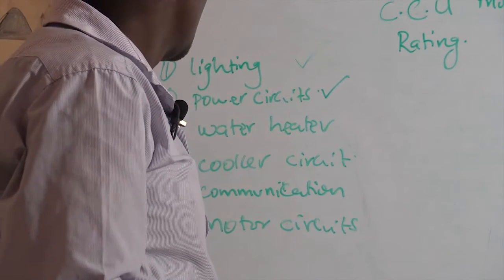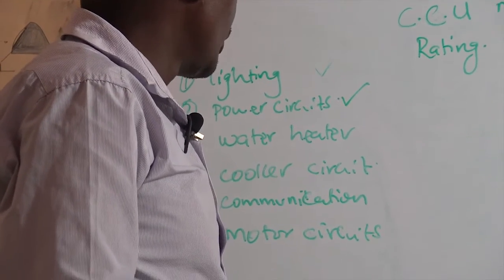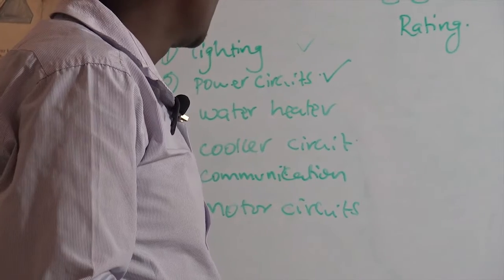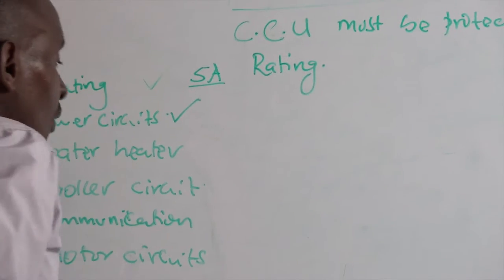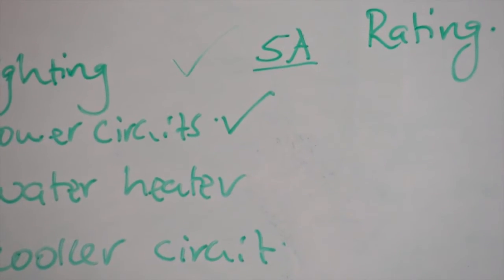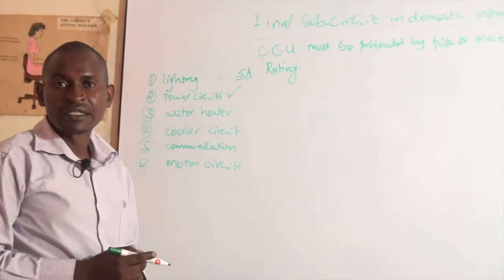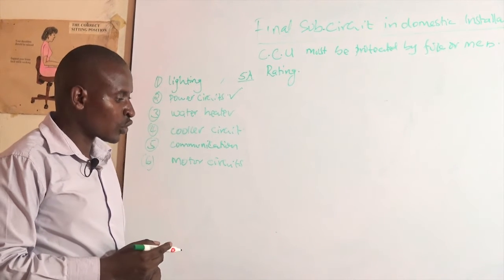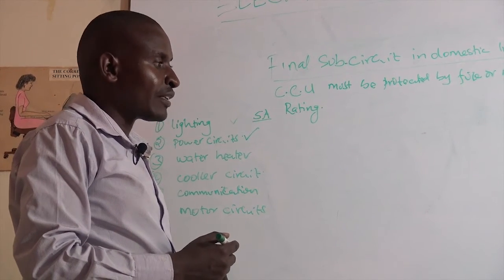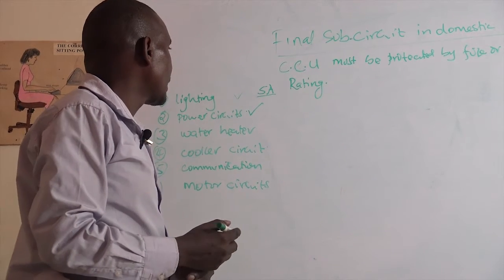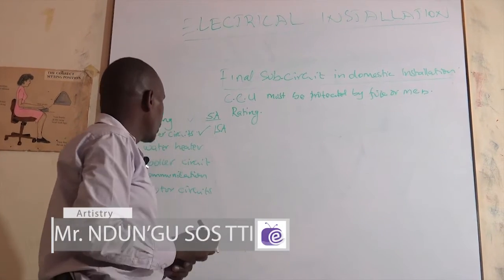All the final sub-circuits have different ratings. For a lighting circuit, the maximum rating allowed is 5 amperes. For a power circuit — this is where we connect portable appliances connected by a plug onto a socket outlet — the rating is 15 amperes and should not exceed 15 amperes.